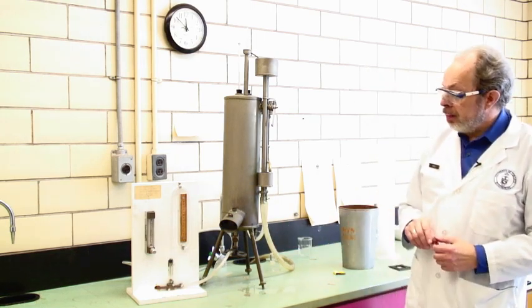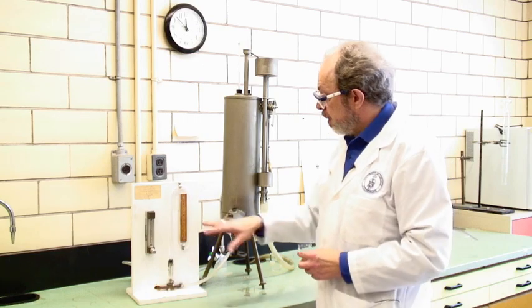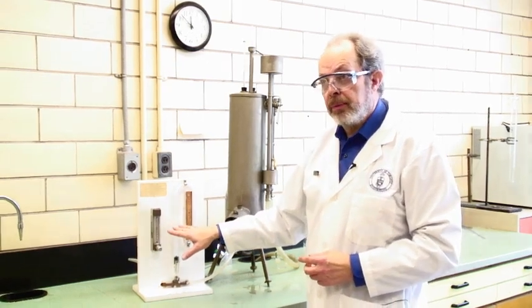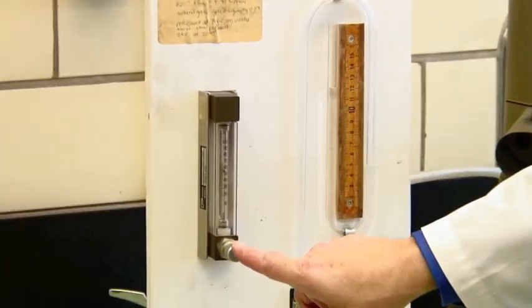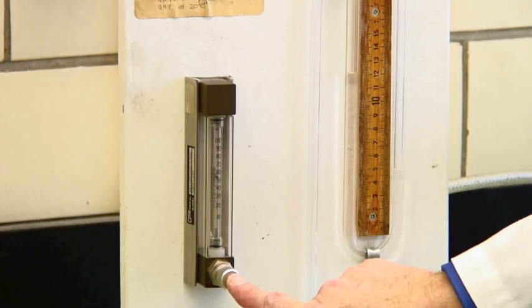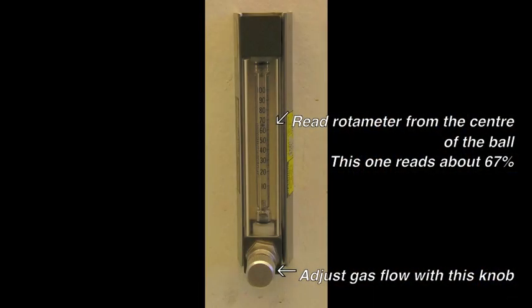The other thing that you need to read is the natural gas rotameter. This knob on the bottom of the rotameter controls how fast the gas is coming through. At the moment it's at about 55 percent. You always read from the middle of the rotameter ball.